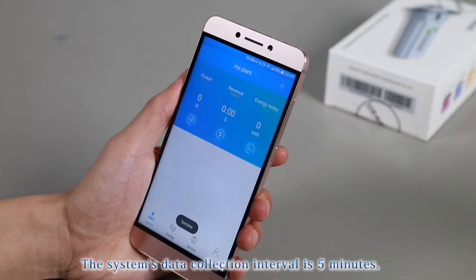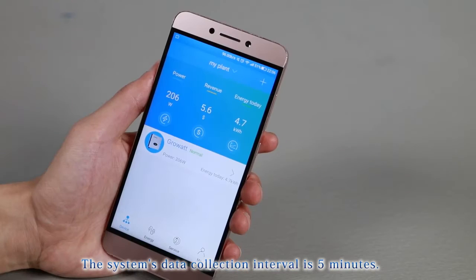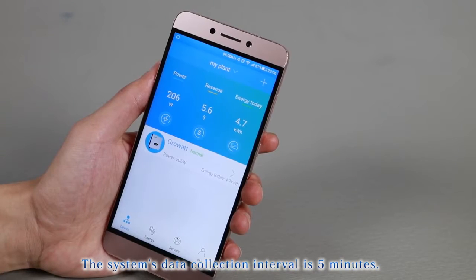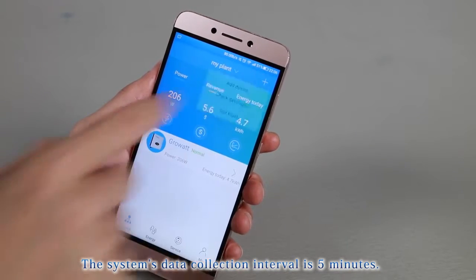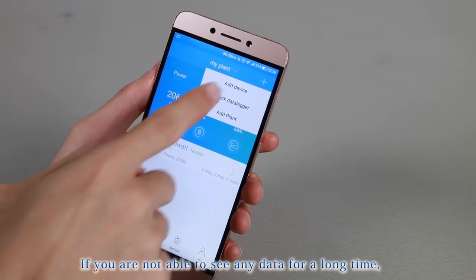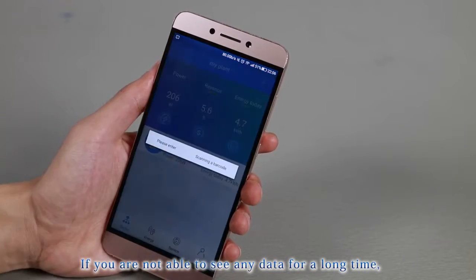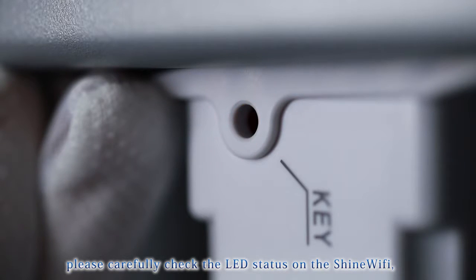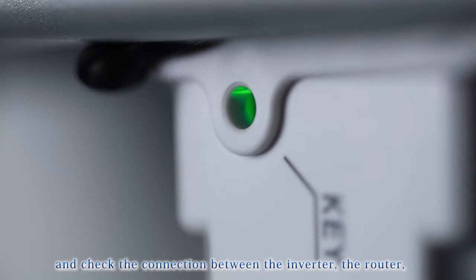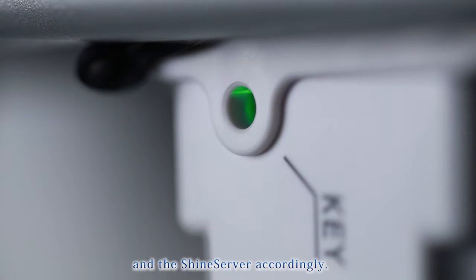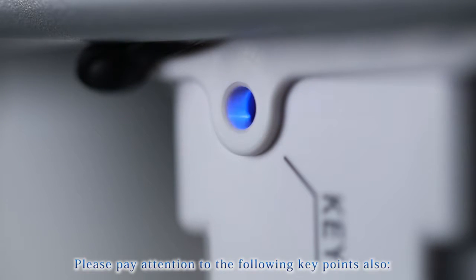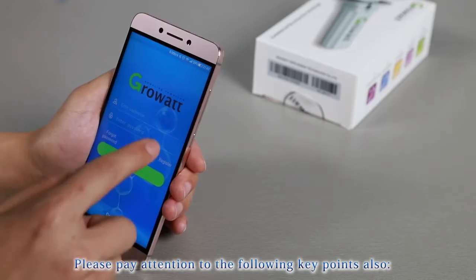The system's data collection interval is five minutes. If you are not able to see any data for a long time, please carefully check the LED status on the Shine Wi-Fi and check the connection between the inverter, the router, and the ShineServer accordingly.